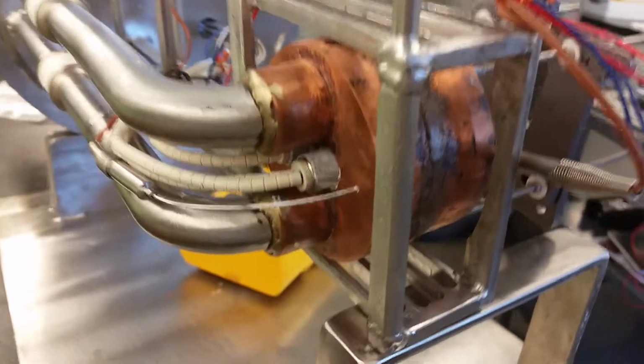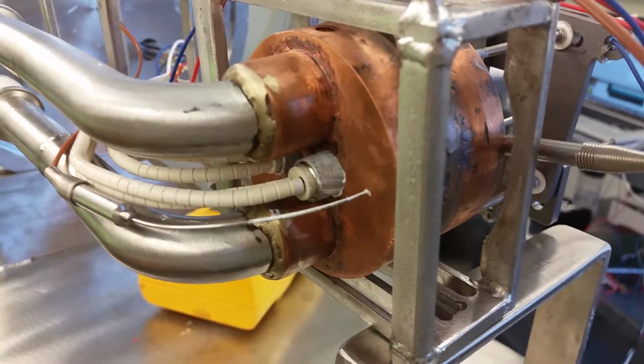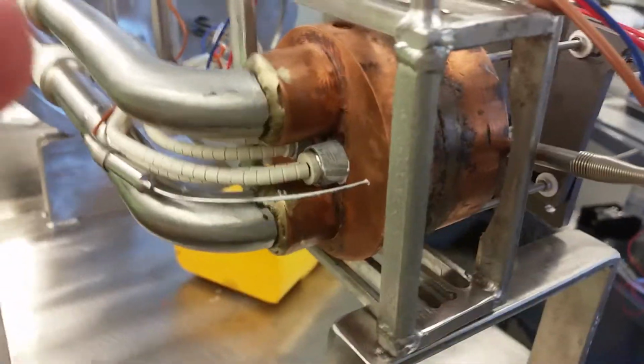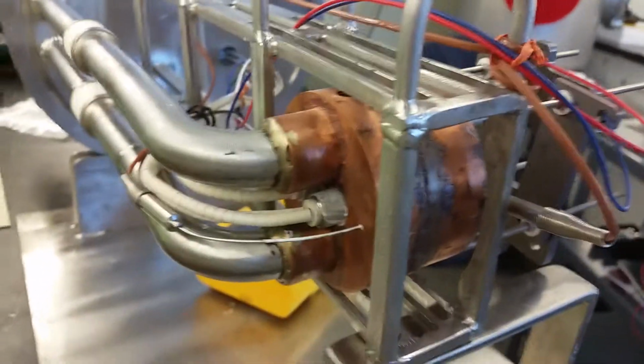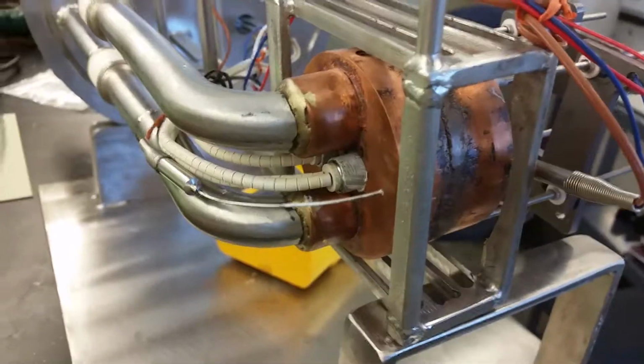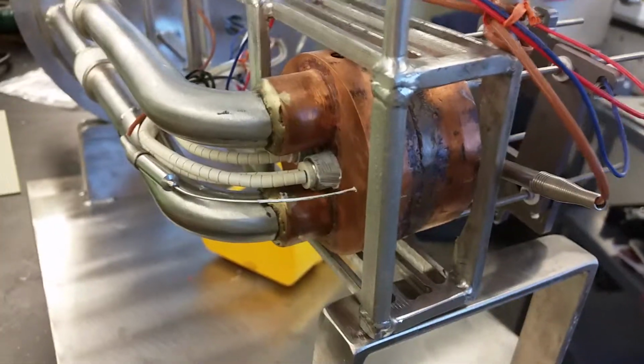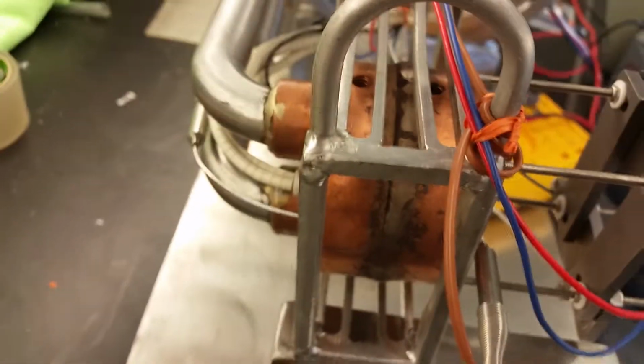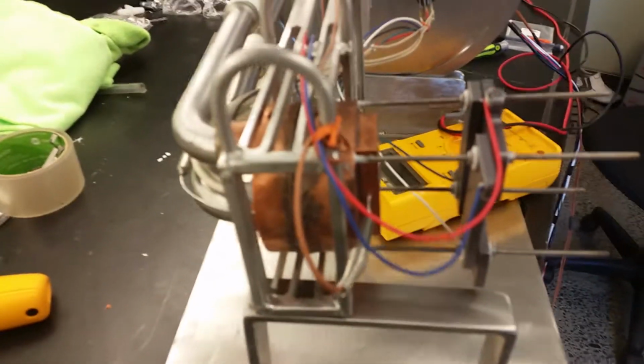What I am going to do is, this copper block has 2 cartridge heaters going into the back, powered by AC current. They feature a nickel chromium coil that acts as a direct resistor to heat this block. When I apply full current to the cartridge heaters, with a couple amps of AC, I get quite a variation in the current I'm trying to read off this copper block.